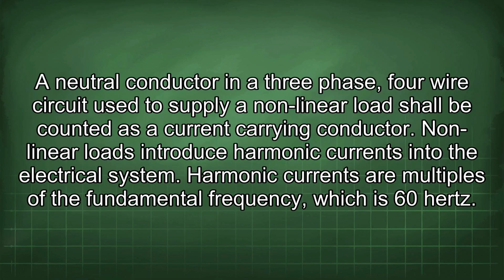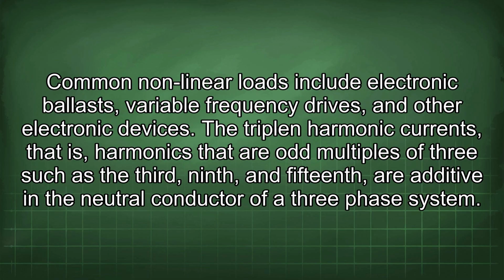A neutral conductor in a 3-phase, 4-wire circuit used to supply a nonlinear load shall be counted as a current-carrying conductor. Nonlinear loads introduce harmonic currents into the electrical system. Harmonic currents are multiples of the fundamental frequency, which is 60 Hz. Common nonlinear loads include electronic ballasts, variable frequency drives, and other electronic devices.